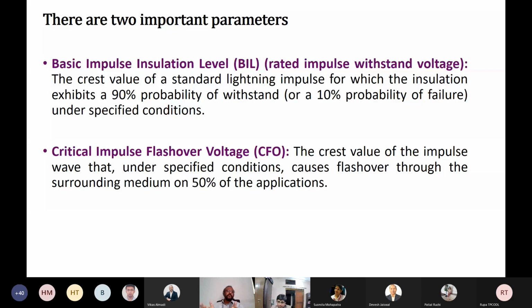Now, I'm sure that most of you know about these things. There are two important parameters when it comes to the lightning protection of MV systems and HV as well: the BIL and the CFO. Keep in mind that these two are somewhat different, because BIL talks about the withstandability, whereas CFO talks more about the failure. So when you are talking about the insulation parameters, this definition should be understood very clearly.